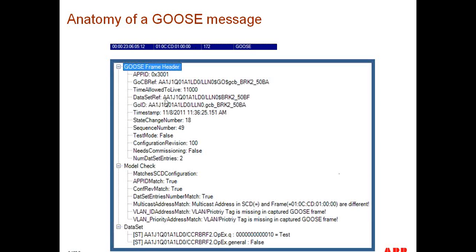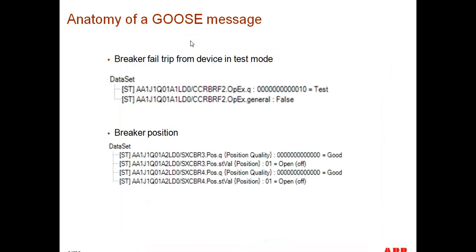If we decode the traffic a little bit, we can see the data set reference, meaning what the data set is and where it is located as part of the SCL. We can see the timestamp, the state change number, and the sequence number. We can see whether the device is in test mode or not, and whether the device needs commissioning or not. And then we can see the information being shared, which in this particular case is a breaker fail function, RBRF, related to protection breaker fail. We have the trip signal, operation execute .general, and the quality.